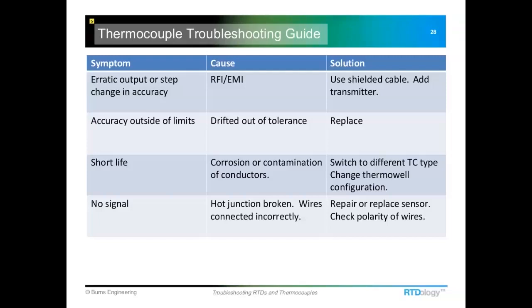One of the drawbacks to thermocouples is that they do drift fairly quickly, especially at higher temperatures. If you're running 1,000–1,500°F, they can drift pretty quickly. You may want to put them on a replacement schedule every six months or a year. There's really no fix — it's just the normal degrading of the thermocouple wire. It can pick up contaminants at higher temperatures, and there's sometimes corrosion that can happen within the sheath.